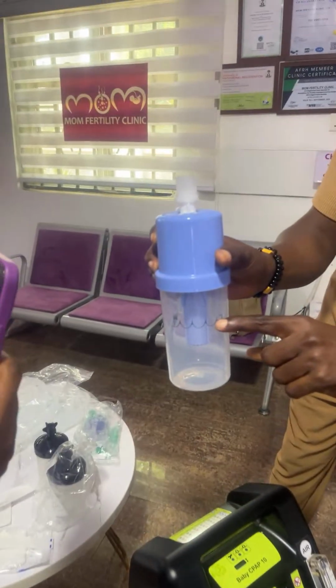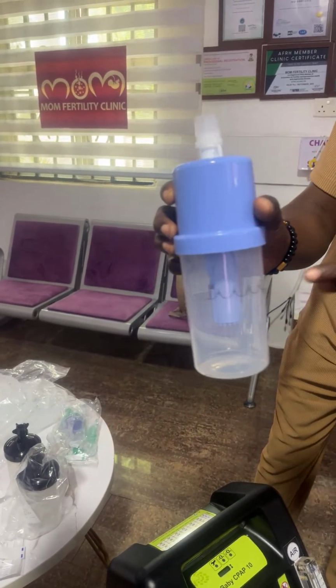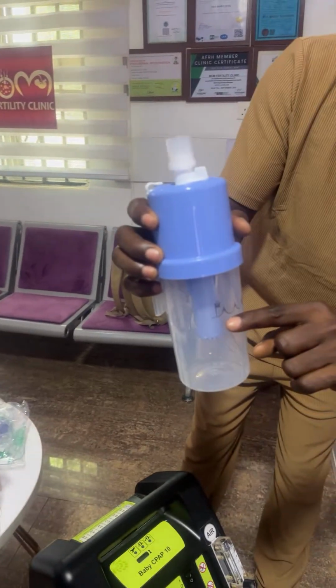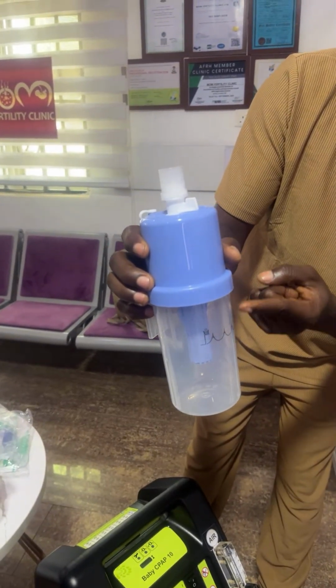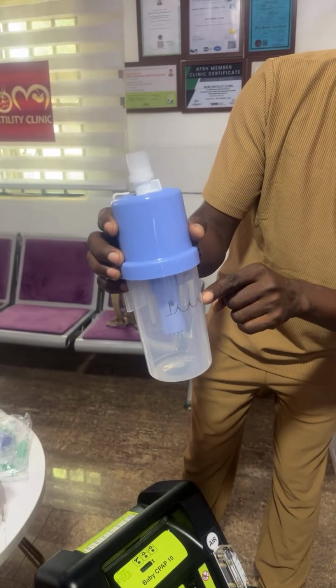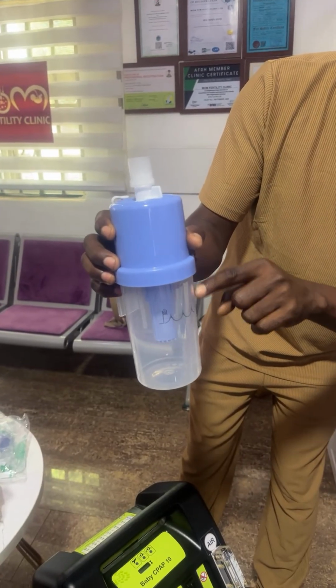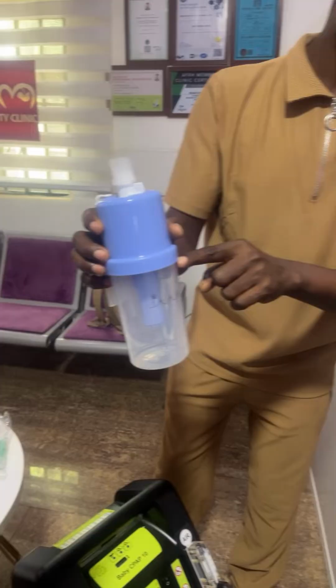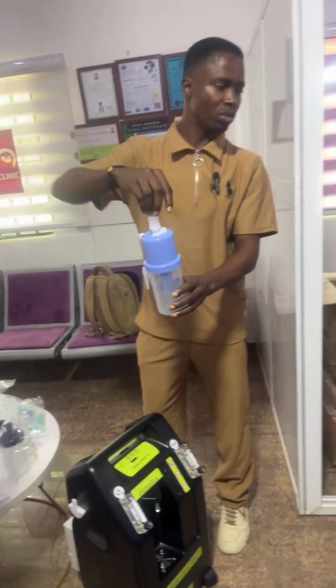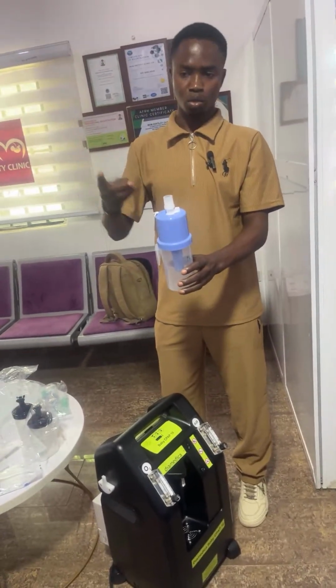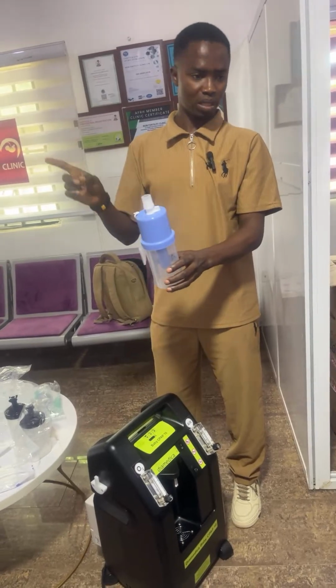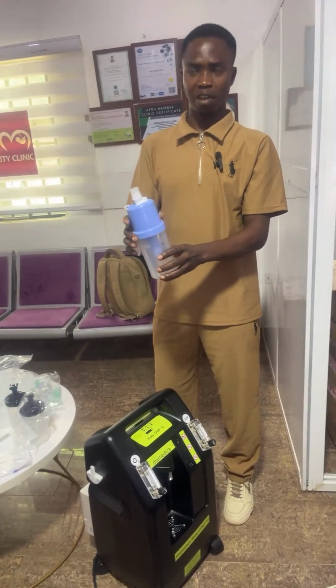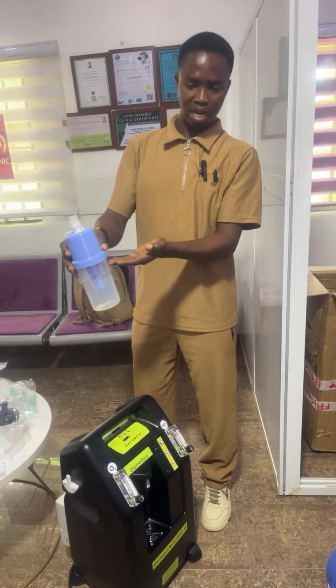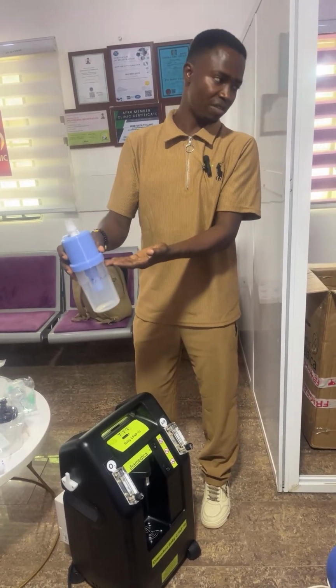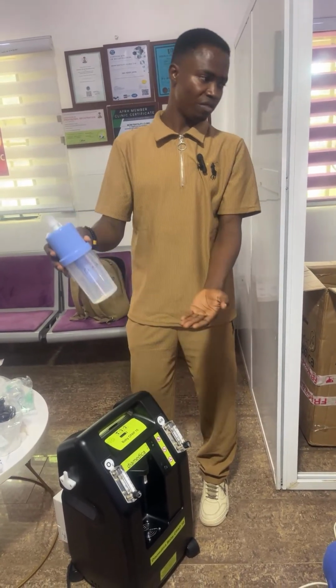So you can see the mark there. Yes, the dash line. So even if it's a little bit lower or a little bit higher, you can still use it, but it must not be above this or this. If it's above, there's a tendency that water will slip back, and also your value will not be correct. You want to give 5 centimeters of water, but the water is above this, so that means you are not giving 5 centimeters. If it's lower, you are not giving 5 centimeters.